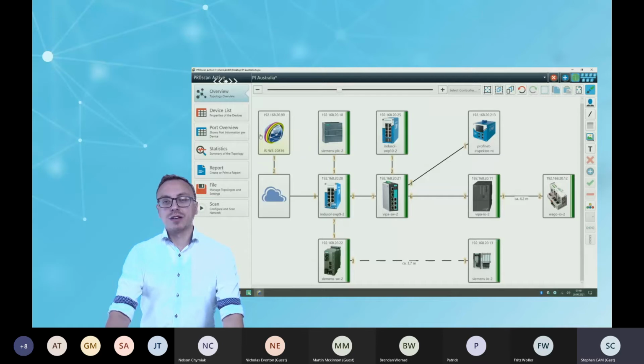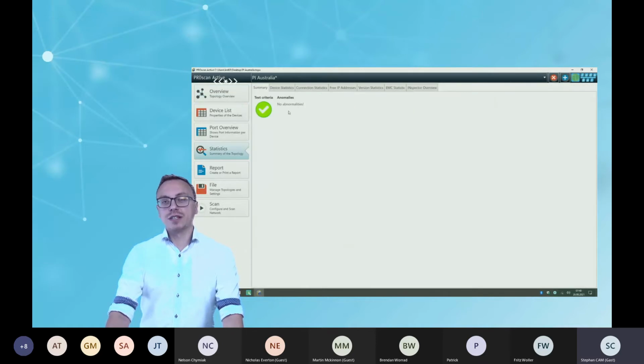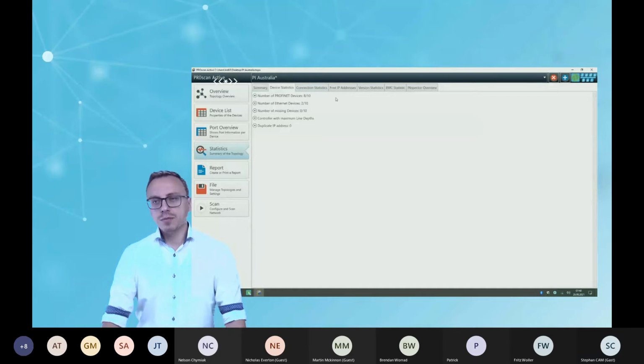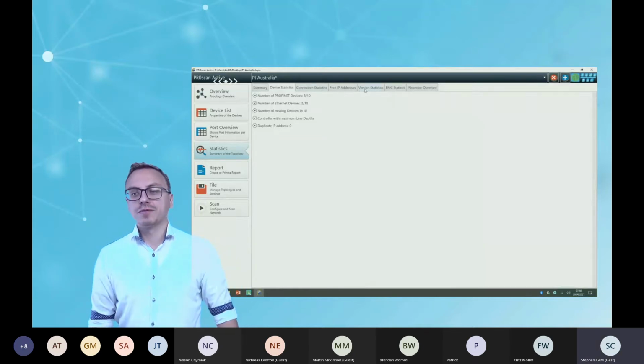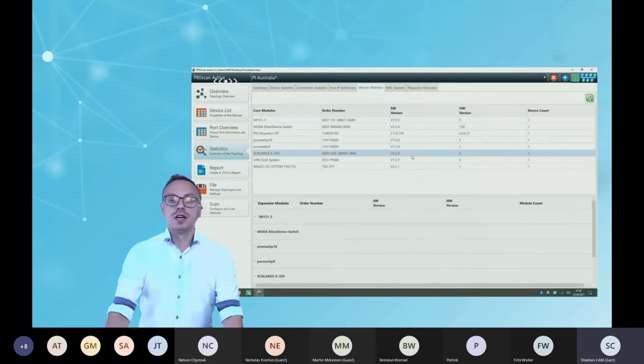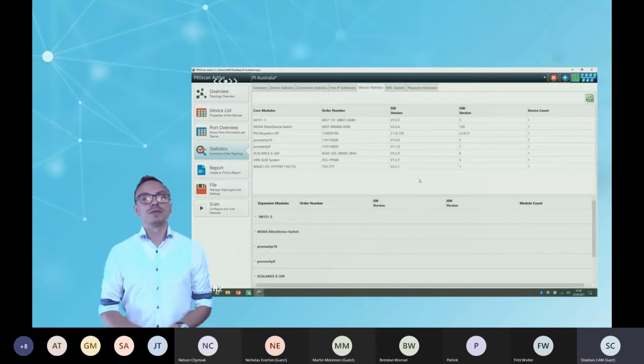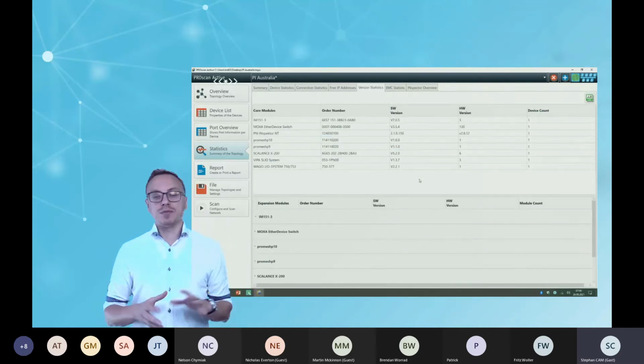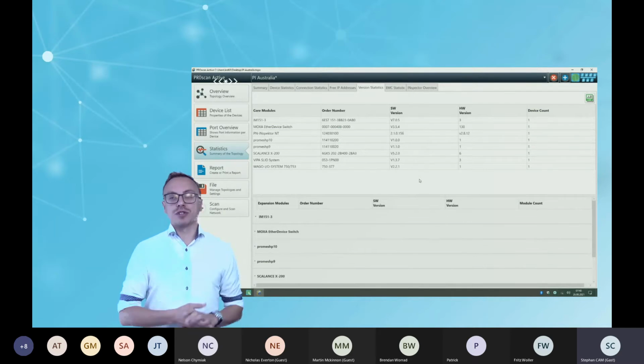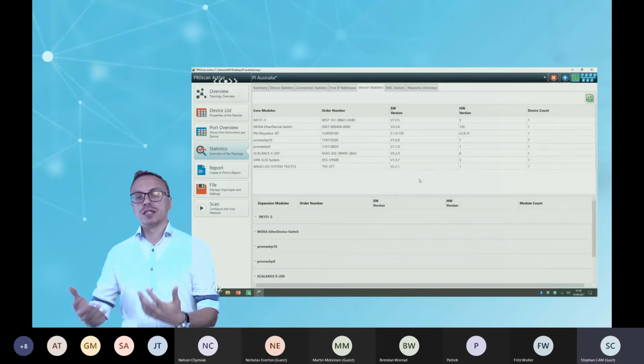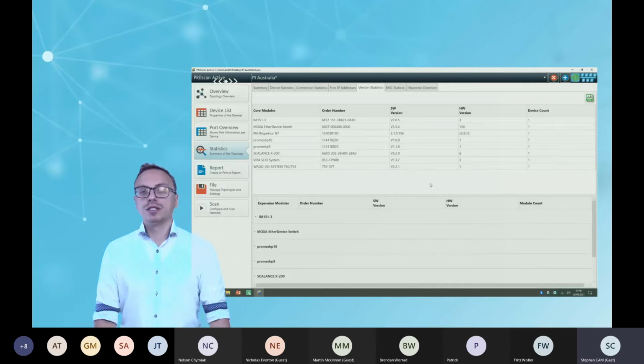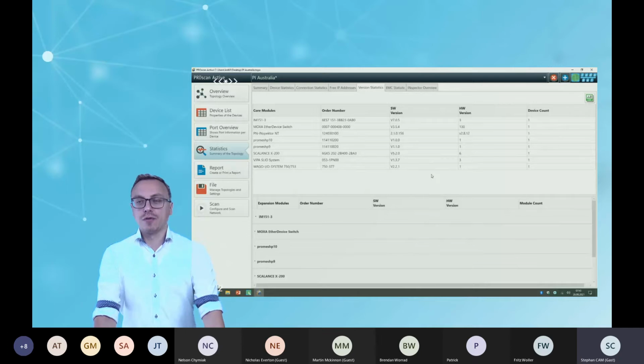So what else do you see in this software? You can go to statistics. You see if you have some issues in your system. You get information about PROFINET devices, missing devices, duplicated IP addresses. But an important function of the software is the version statistic, because the recommendation from the PI is that all devices of the same type have to have the same firmware version in your system. So if you have a lot of ET200, for example, in your system, the ET200 have to have the same firmware. This is what you can test very easily with this software as well.